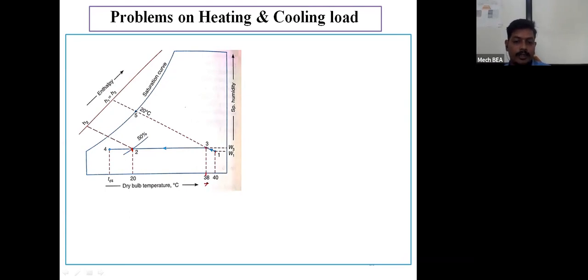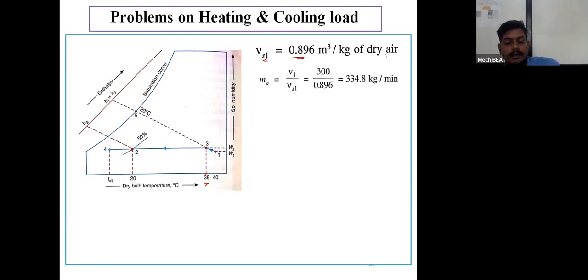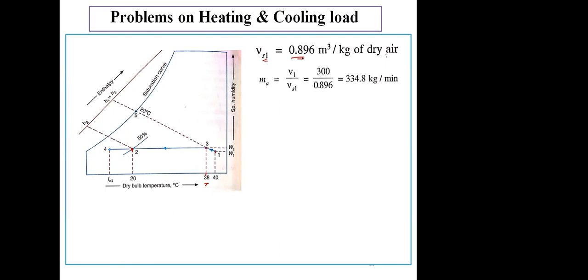So based on that point number 3, I will calculate the value of TD3. Here actual value of TD3 is 38 degrees centigrade. So first of all, here to calculate the value of mass of air corresponding to point number 1, by using the psychrometric chart I will calculate the specific volume, which is 0.896 meter cube per kg. Mass of air will be equal to volume divided by specific volume of point number 1, which is 300 divided by 0.896, so I will get mass of air as 334.8 kg per minute.